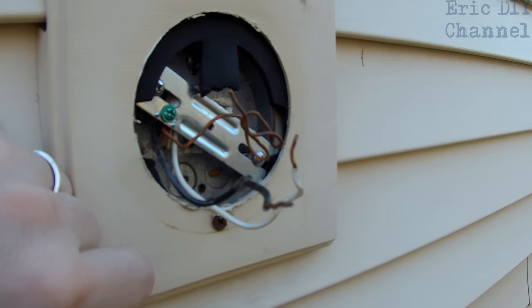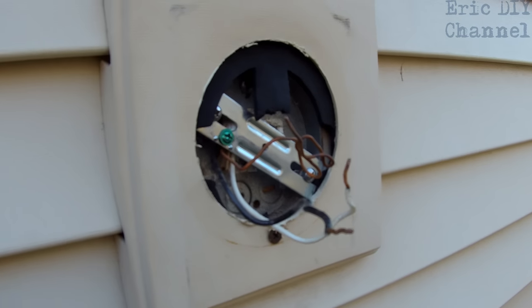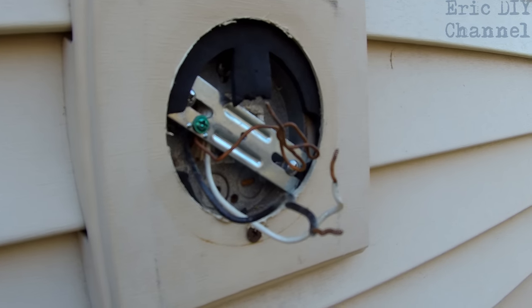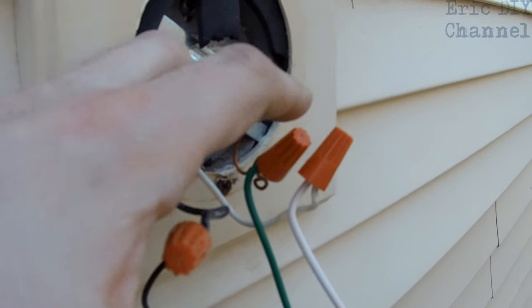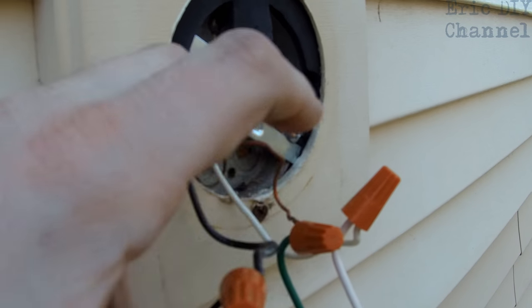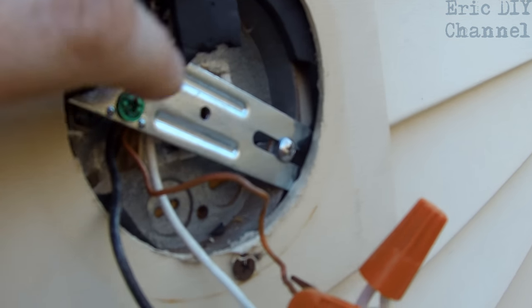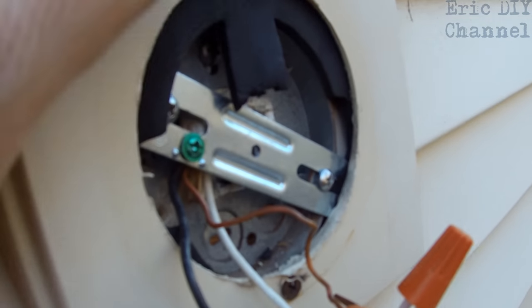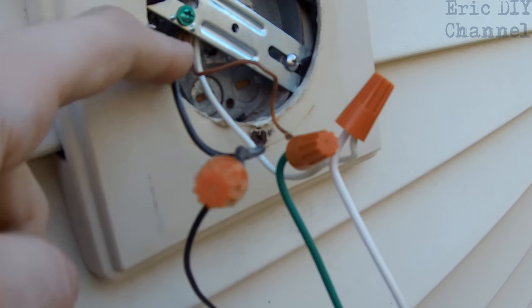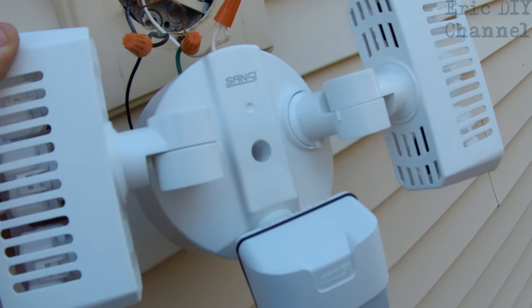We're going to connect the wires up using the wire connectors. Remember, make sure there's no power — I tested it before touching it. We wired it black to black, green to bare copper wire which is your ground, and white to white. You can also have the bare copper wire connect here for additional grounding right at the source. Now we're going to carefully tuck these wires in and mount the SANSI LED motion sensor light.